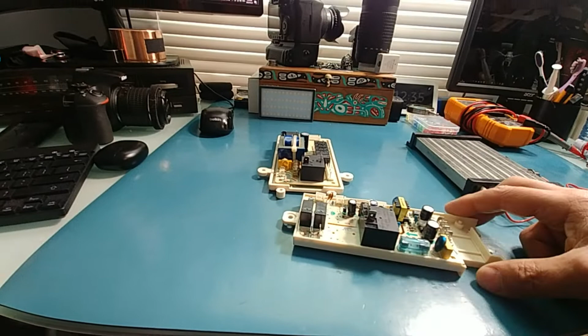These ones here are the same. This is an indoor unit that had pipes going out the window, with dual contacts at 250 volts at 30 amp. These will latch at 12 or 13 volts no problem, at very low amps, under an amp, to latch them.